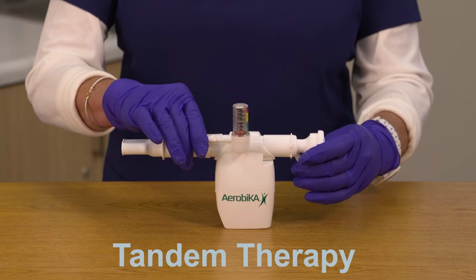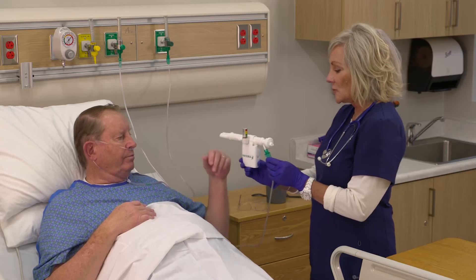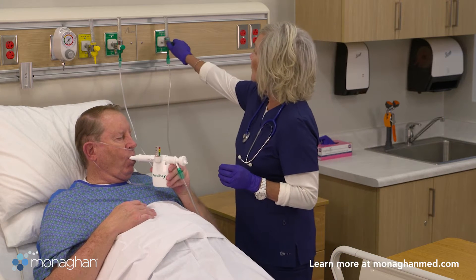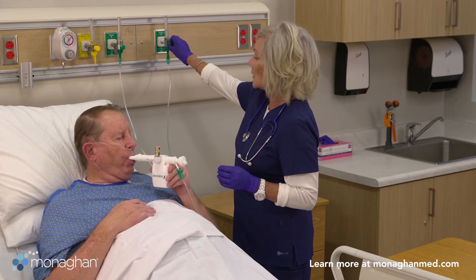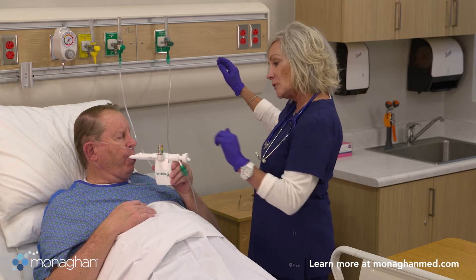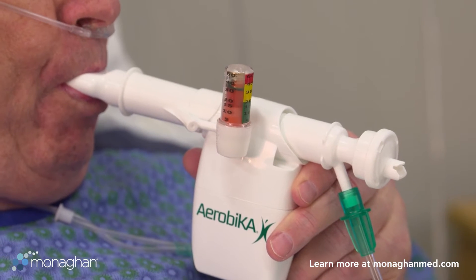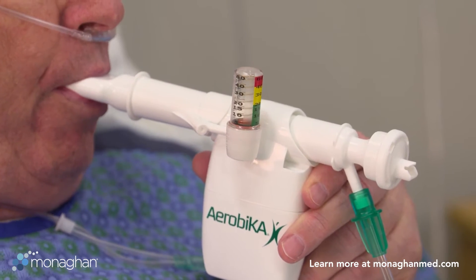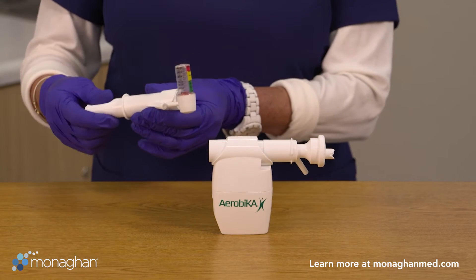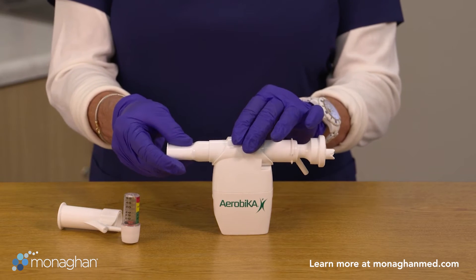The addition of the AerobiKA oscillatory positive expiratory pressure device to the VersaPAP device requires no additional adapters or connectors. When combined for tandem therapy, the devices work together to provide positive airway pressure on both inspiration and exhalation, opening and recruiting airways with every breath. Oscillations are present only on exhalation to help mobilize and move secretions out of the lungs.